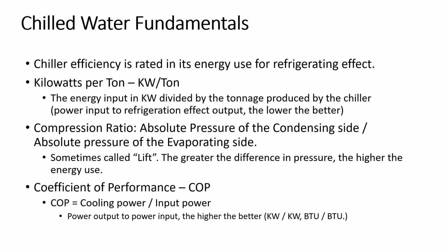So like for heat pumps, you'll see ratios of 3 because the energy used to produce the heat is not an equal thing like your electric heat. So you actually are using less energy to produce more heat. It's not produce, it moves heat. So you put in energy and you move 3 times more. In the case of a heat pump, we're talking refrigeration, that goes the other way, but you have to compare power to power or BTUs to BTUs to use COP.